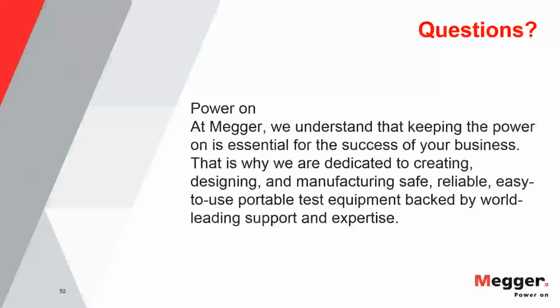And customers approached us to ask, hey, can we do the PD test with cosine rectangular as well? And to be very honest, we said, well, let's see. Then qualification studies were made, which showed that the CR technology gives you, like DAC, power frequency comparable results. And this is how this evolved.